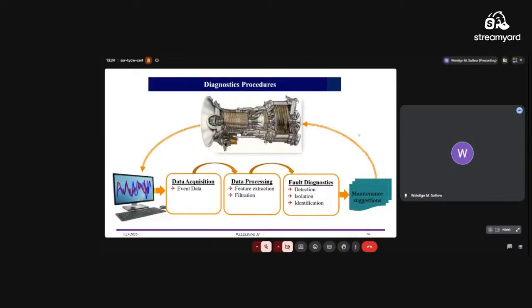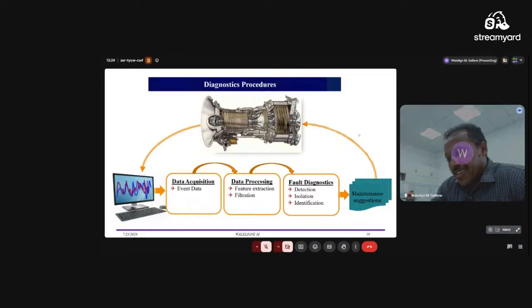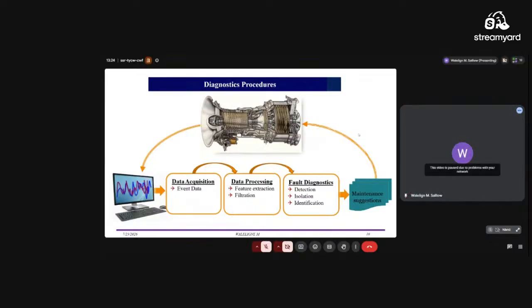So if we have all of these problems in gas turbine, how do we tackle this problem? How do we offset when we have a performance deterioration in the system? So we need a condition monitoring tool, a diagnostics tool. And how do you develop that tool? What are the procedures? The first thing is data acquisition, collecting the event data and the performance data. The second stage is processing the data. And the third stage is developing the diagnostics model, which is the condition monitoring strategy. So it has three packages: the first one is detection, the second one is isolation, and the third one is fault identification.